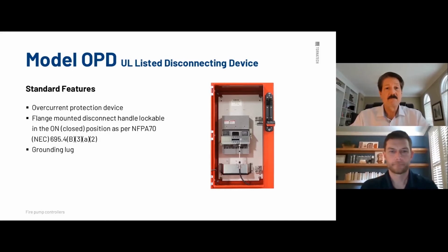Again, it is a flange-mounted disconnect device. It's lockable, and that's the key. Lockable in the on position, lockable in the off position. And you do have a grounding lug. In some situations, municipalities, there are requirements. People want to see a neutral lug that is bonded at the grounding lug. That's an option. You know, let us know.